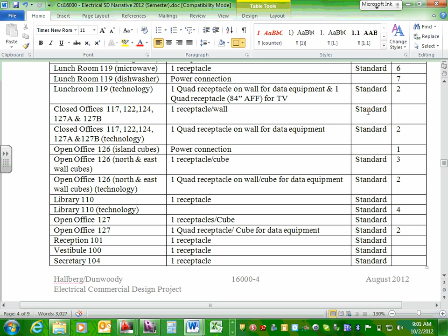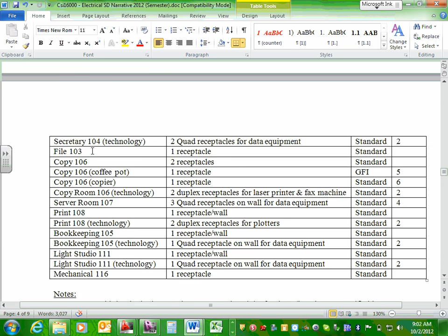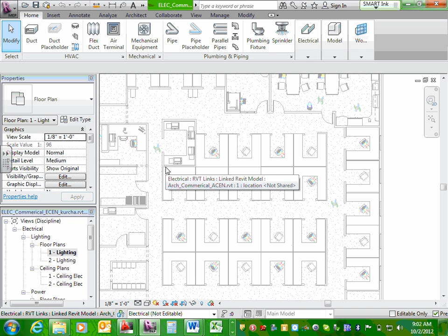It also talks about the open office floor boxes. If you read note 1—can you flip to the 4th line there, Chad? These island cubes, as we call them, are powered modular furniture, meaning the receptacles are already built into the cubes. So what you need to do is go underground and bring power to a single point and connect to these cubes, and the receptacles are already built in.